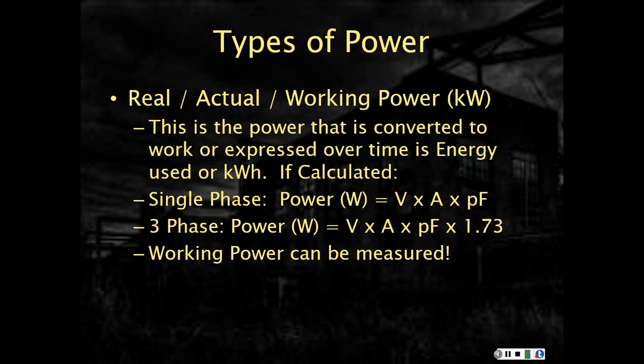Let's take a look at the actual types of power again that make up power factor. In a building, or an electrical distribution system, AC, we actually have 3 types of power. The first type of power, the power that's actually used in a building, is called real, or actual, or working power, and its units are kW. If it's calculated in a single-phase system, power, or W, is volts times amps times power factor. In a 3-phase system, power, or W, is volts times amps times power factor, similar to single phase, times 1.73. It's important to realize that this type of power, the one that's actually converted to work in a building, can be measured with a meter.